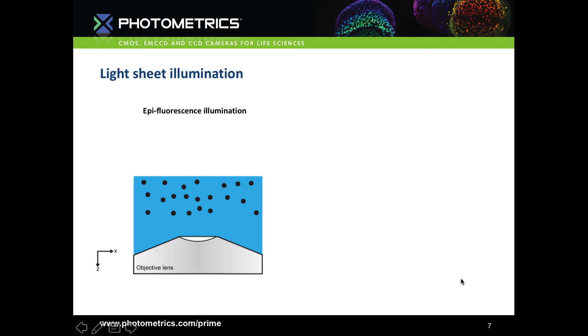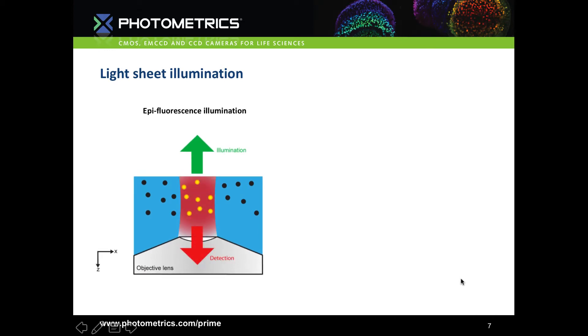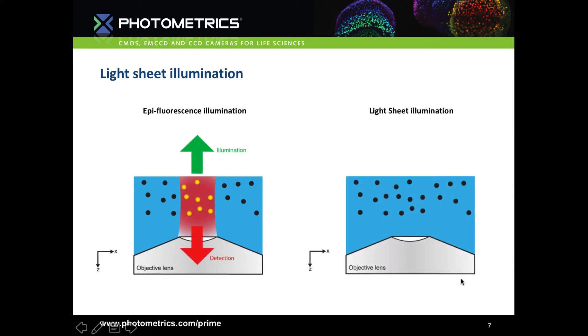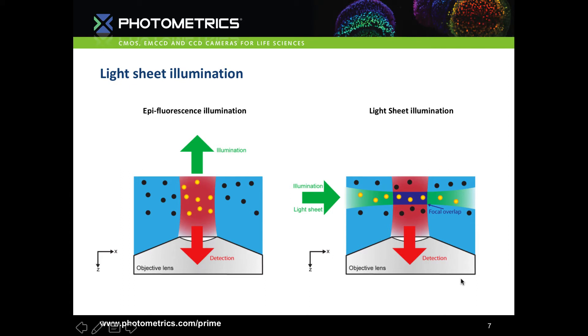The first thing to look at is how we get the light in. With epifluorescence we use the same objective for illumination and detection, illuminating the whole sample. With lightsheet illumination instead, we introduce the light from the side and image at the focal overlap for detection. So we're only illuminating the plane we're interested in, not the whole sample.